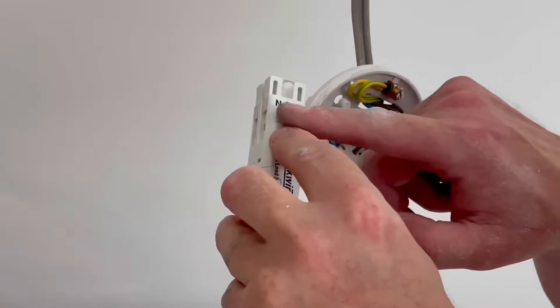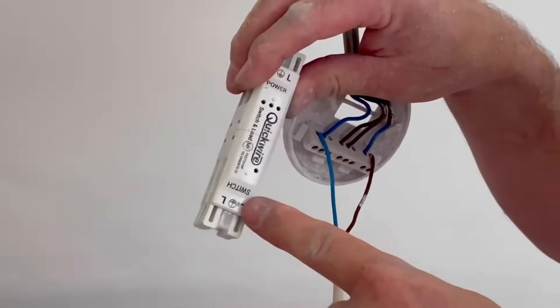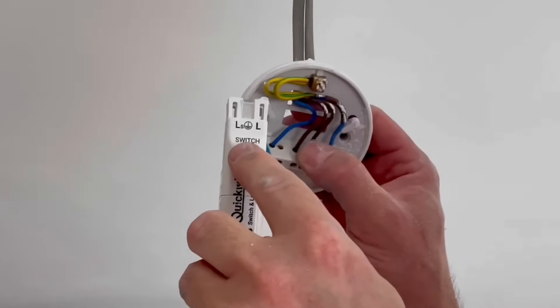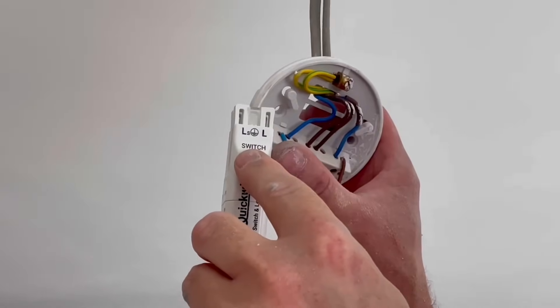So we're going to bring in our line, neutral and CPC and make our connections into here. On the other side as I turn it round we've got the switch one so we'll have our permanent line and switching line connections along with the CPC going into here.